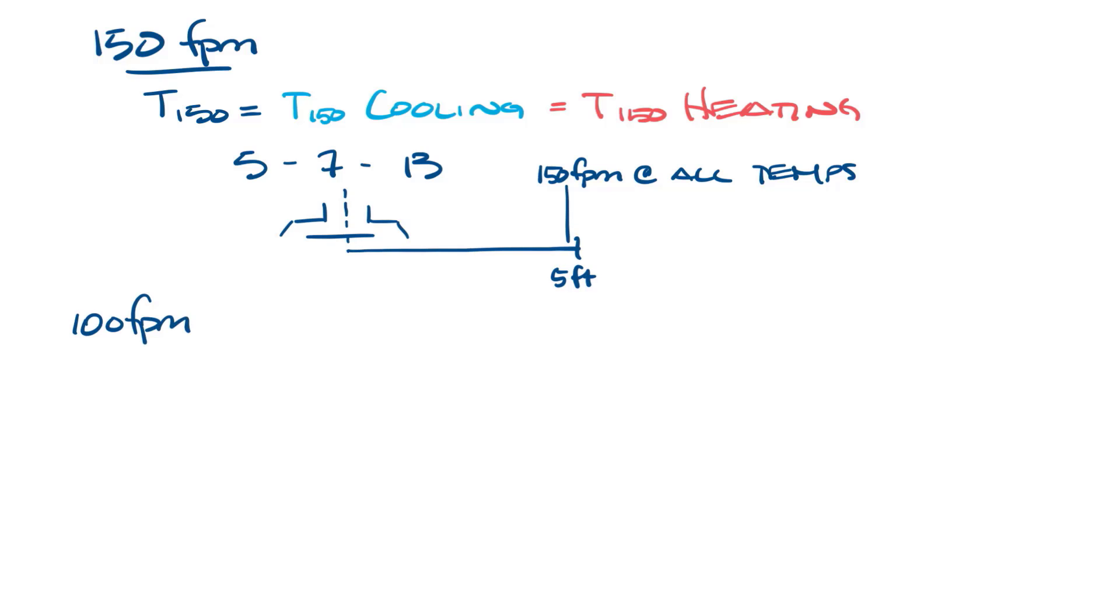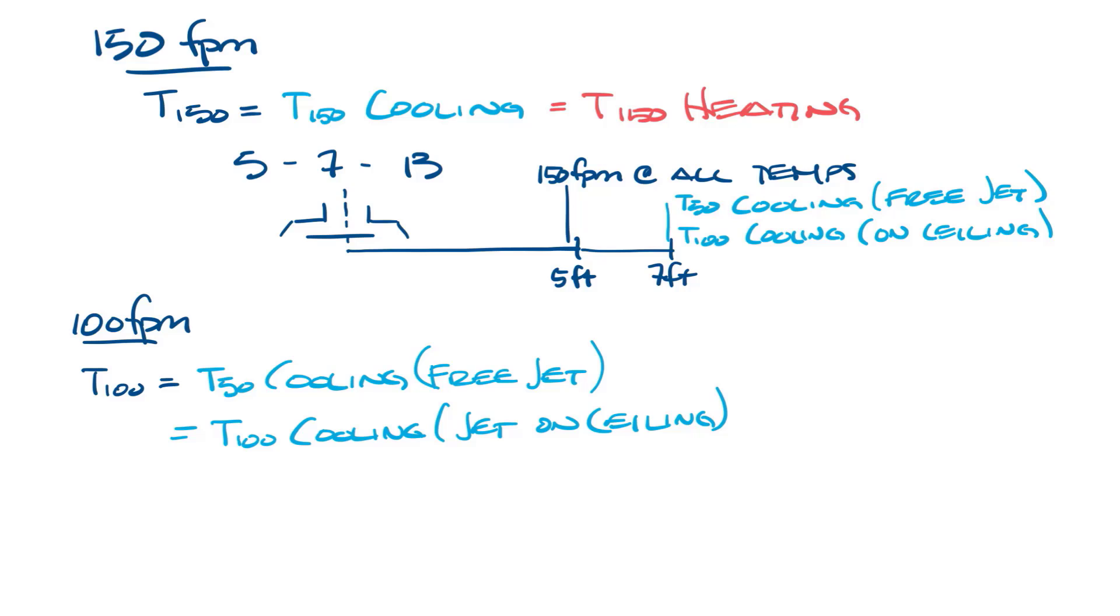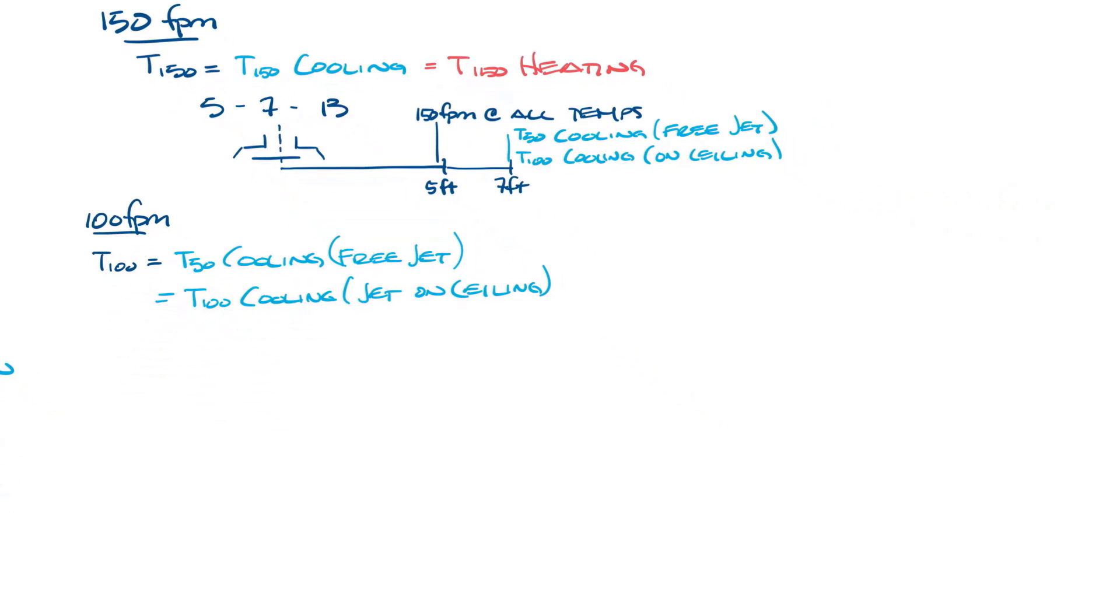So let's talk about T100. The 100 foot per minute catalog throw number is useful because in cooling, the 100 foot per minute isothermal throw is equal to 50 foot per minute cooling throw for free jet, or a 100 foot per minute cooling throw if it's moving along a wall. So let's draw this in up here, T50 for free jet or T100 in cooling if it's on the ceiling. Now let's move this over and look at why it matters if it's moving along a surface or not.